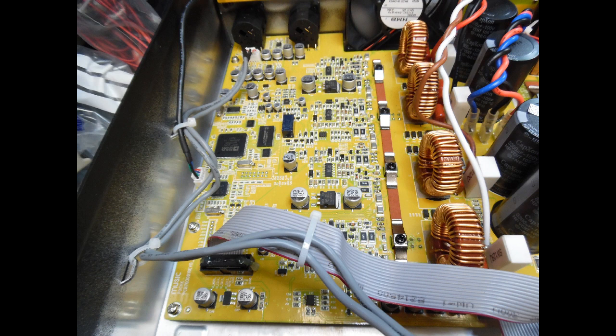And this is what I was mentioning previously. On more complex designs, you need to determine if it's the amplifier causing the issue that's triggering the protection circuit, or if the protection circuit itself is faulty. I can disconnect the main amplifier board from the switch mode power supply to determine that easily, because as soon as I disconnect the main amplifier, I can run the switch mode power supply offload and make the necessary measurements and tests.